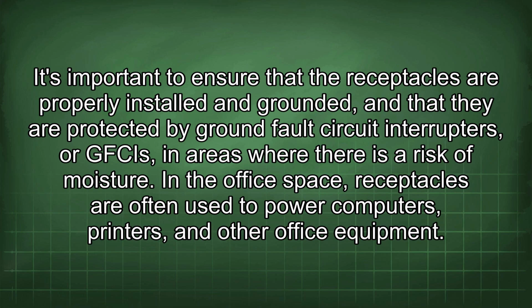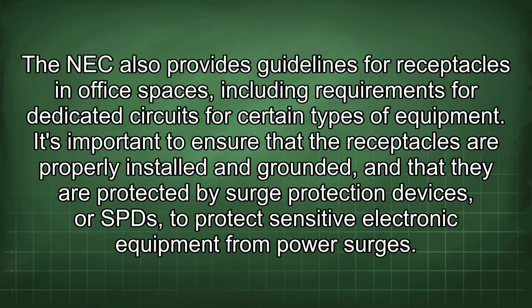In the office space, receptacles are often used to power computers, printers, and other office equipment. The NEC also provides guidelines for receptacles in office spaces, including requirements for dedicated circuits for certain types of equipment. It's important to ensure that the receptacles are properly installed and grounded, and that they are protected by surge protection devices, or SPDs, to protect sensitive electronic equipment from power surges.